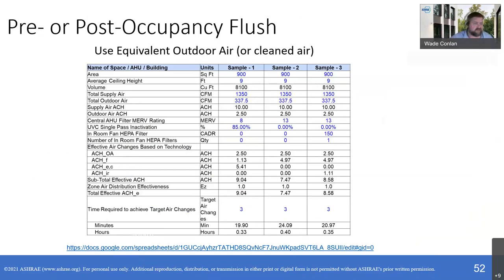As noted, it's the flushing calculator. So you have the 3, you can change that to a 5 if you want, and you can see the time frame it's going to take to flush that space between uses. Now, the one thing I do want to point out: the documentation says 2 hours, and there's a reason for that. As engineers, we have to be conservative. We looked at units and said, okay, let's say you had the outdoor air dampers shut. You're going to get a couple percent of outdoor air, and they had MERV 5 filters. That gets you in that 2 hour range. We basically said, here's your potential worst case scenario, what does that look like? And that's where you end up at 2 hours. So doing these calculations is very valuable to save energy. Next slide.